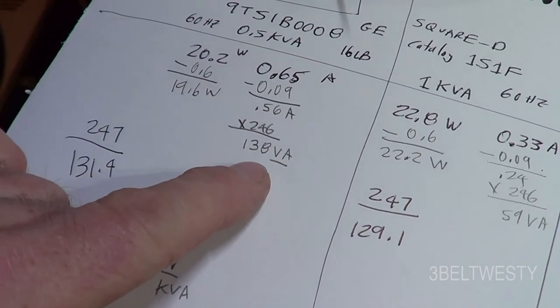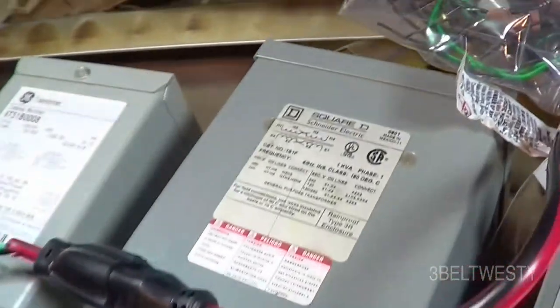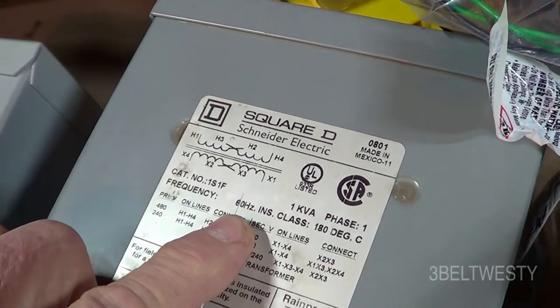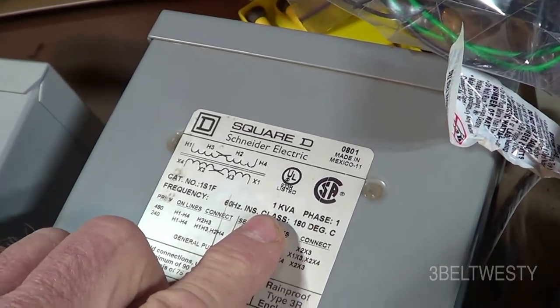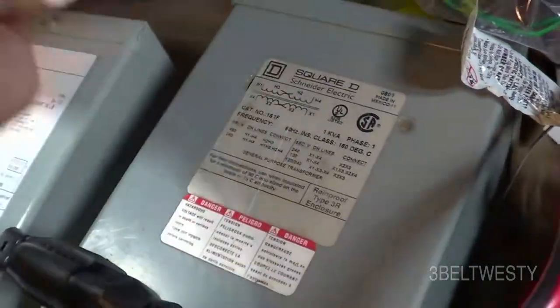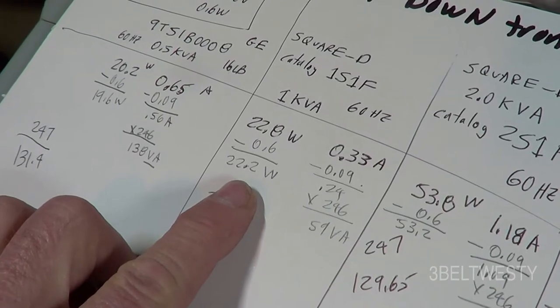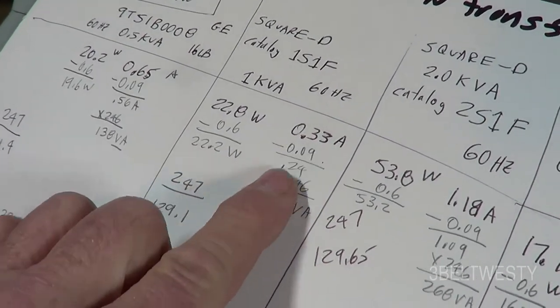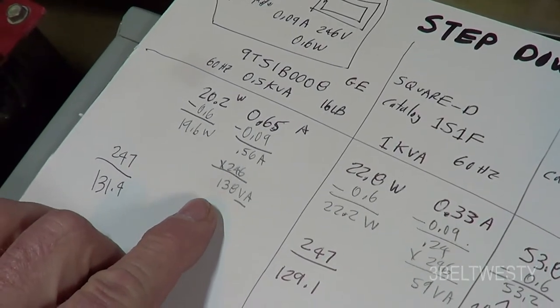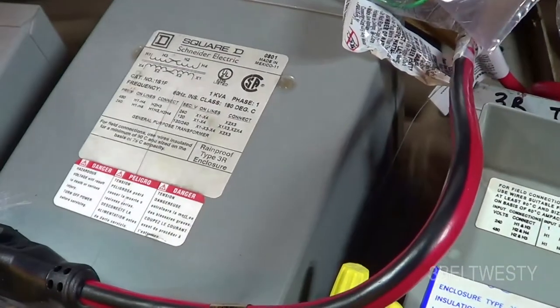The Square D unit is a 1S1F, 60 Hz, 1 kVA. It's wired 240 in and 120 out. It only takes 22.2 watts to run at no load, and the current is 0.24 amps — so 59 volt-amperes. Compare that to the GE at 138 volt-amperes no-load. This Square D may have better steel and it's a larger transformer.